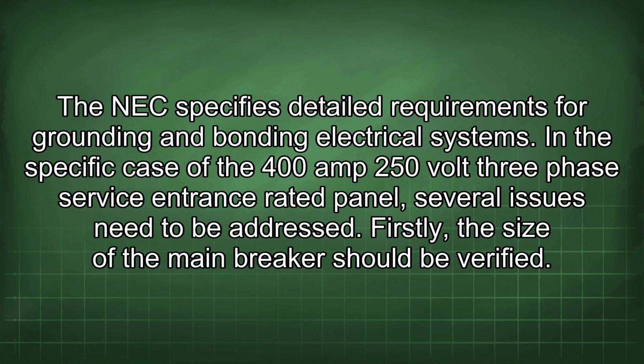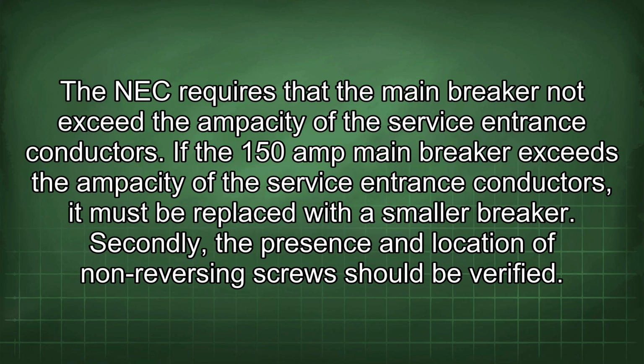In the specific case of the 400 amp 250 volt 3-phase service entrance rated panel, several issues need to be addressed. Firstly, the size of the main breaker should be verified. The NEC requires that the main breaker not exceed the ampacity of the service entrance conductors. If the 150 amp main breaker exceeds the ampacity of the service entrance conductors, it must be replaced with a smaller breaker. Secondly, the presence and location of non-reversing screws should be verified.